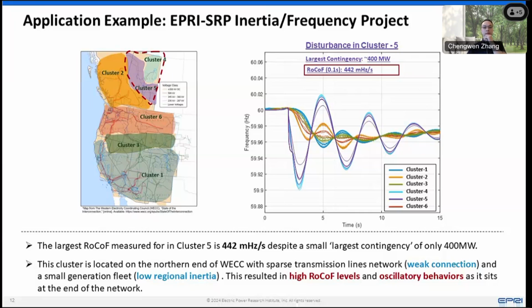You can see the light blue and purple curves here. Those are the frequencies measured in the Alberta region in clusters 4 and 5 on top. The reason we're seeing this goes back to two major factors: there is a limited number of generators in this region, so it has lower regional inertia, and also this region is very weakly connected to the rest of the system. That makes it easy to have regional dynamics that are so different from the rest of the system.